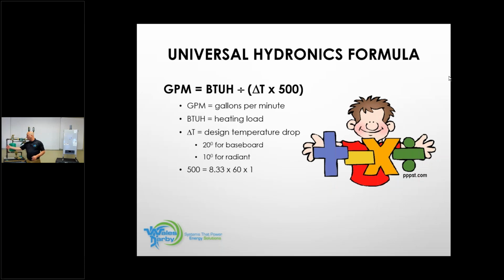So as I'm sending water out of here, I'm flowing water out of here, GPM, right? GPM equals BTU divided by delta T times 500. So now that delta T times 500, I just told you that's 10,000, so you could write 10,000 BTU above that. So I now have heat going out at 180, let's call it. It's going out through my heat emitters.